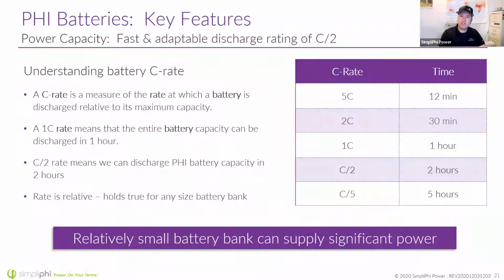The ability to charge and discharge a battery quickly is crucial. If you have a generator running at full power, it can charge the batteries up in a quick time window and then be shut off. Our batteries have a C rate of 2, or C over 2, meaning you can charge or discharge them completely in a 2-hour period. Lead acid batteries, by comparison, are often C over 20 or C over 10, or C over 5 if you're really hammering on them. Lead acid battery capacity is rated at its C over 20 rate, and once you discharge faster than that, its effective capacity is actually much lower.